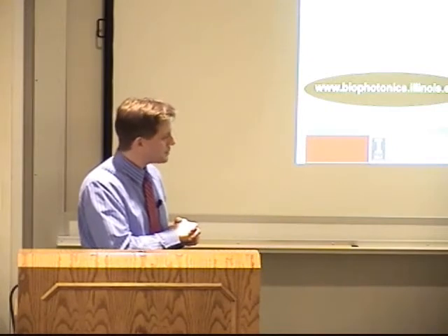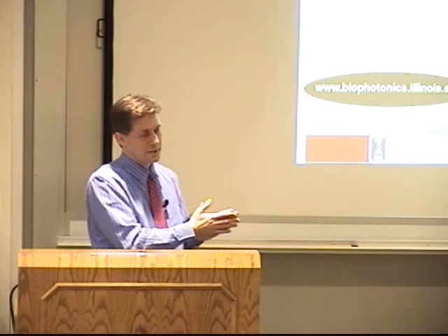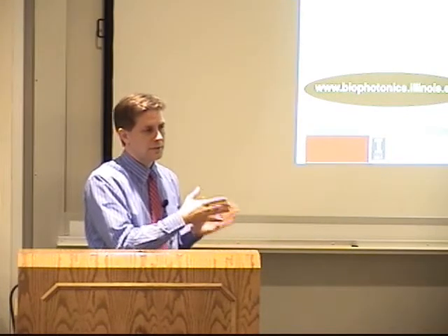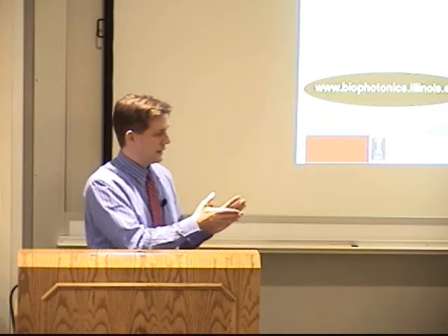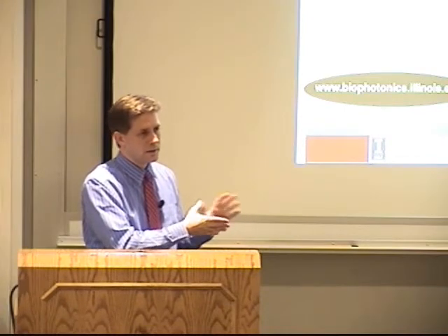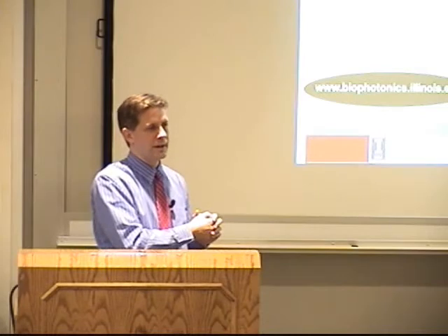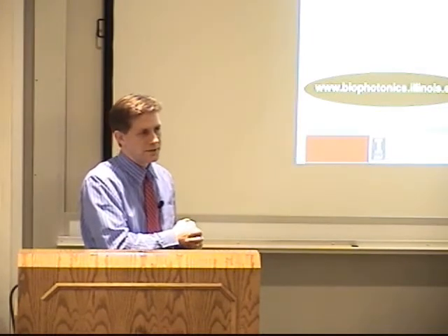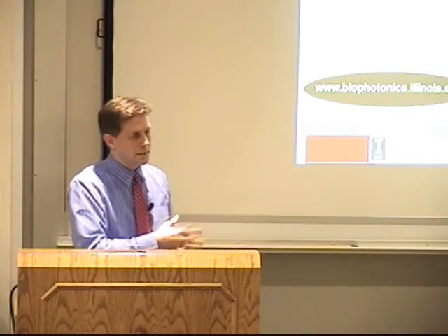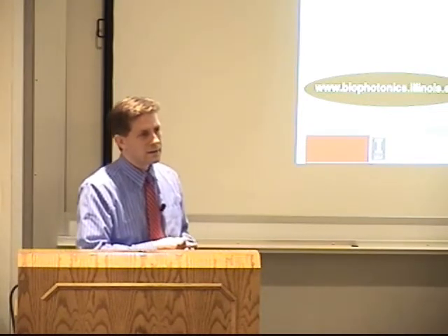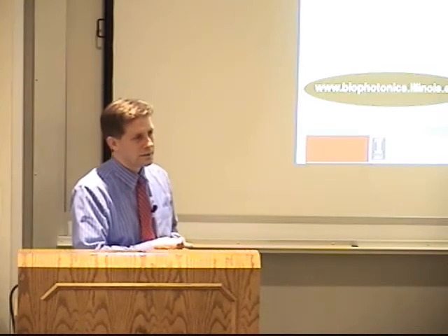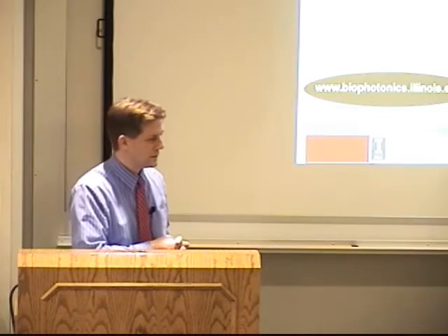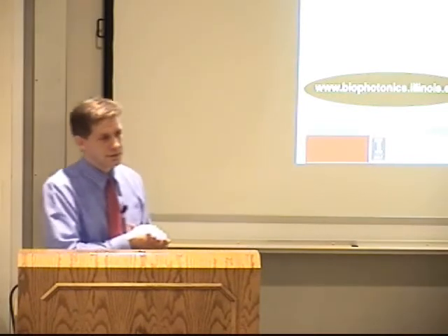Now with ISAM, the changes that have to happen are really to ensure phase stability, and you have to oversample the tissue a little bit more in order to feed that ISAM algorithm. The videos that we showed were ISAM done in real time. So we are able to go at about 2 frames per second with that ISAM processing, a factor of about 8 times slower than OCT.